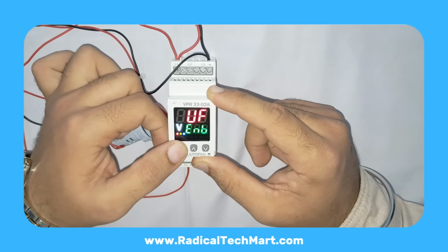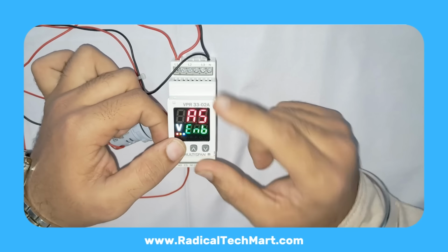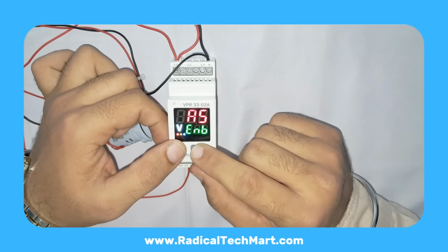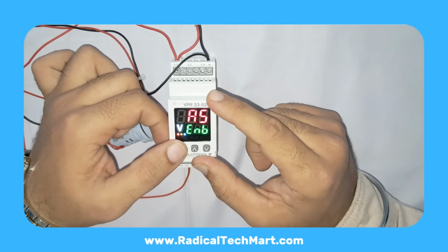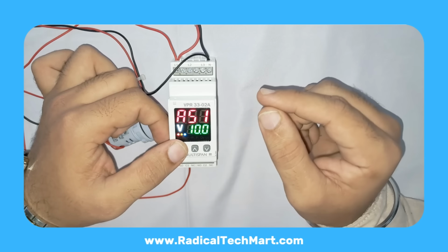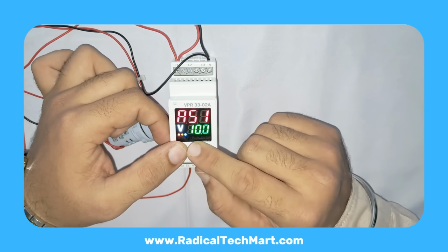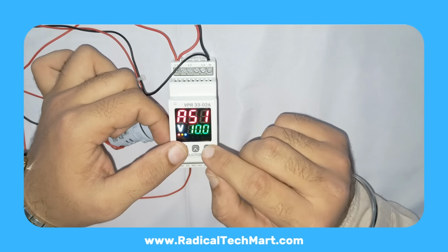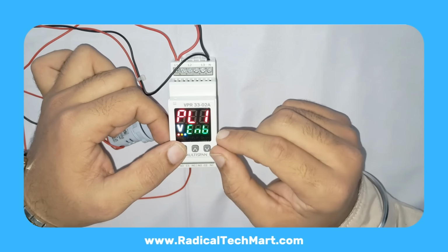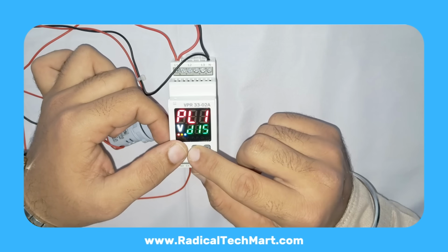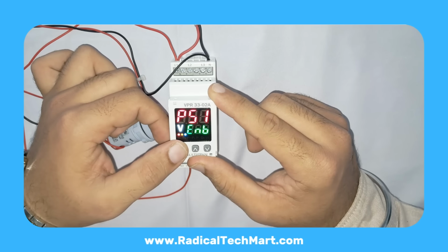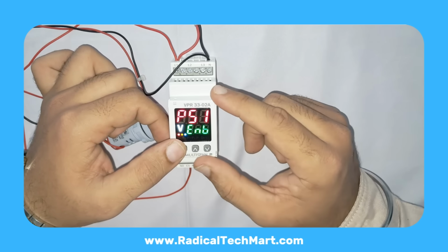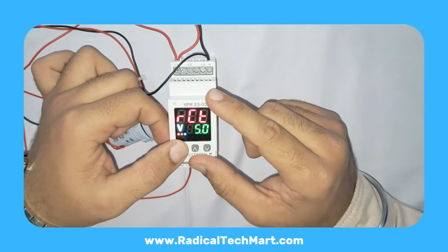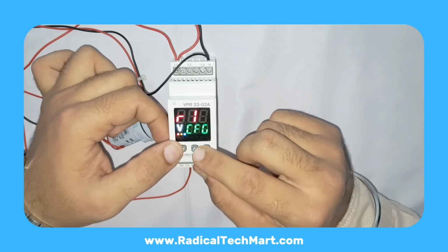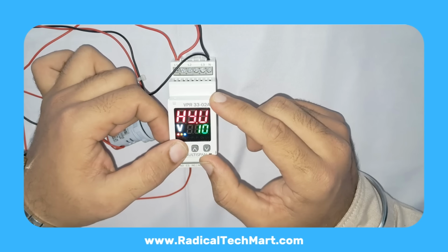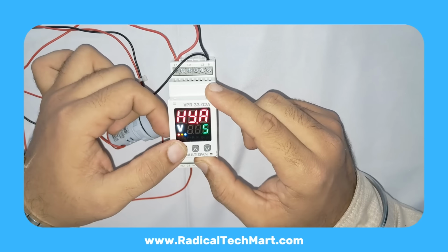Asymmetry, ASY. Phase loss and phase sequence. For asymmetry, you can enable or disable it. This monitors the voltage difference between phases. The default may be a 10-volt difference, which you can adjust. For phase loss, you can choose whether to detect and trip on loss of any phase. For phase sequence, you can enable/disable wrong phase sequence protection. When reset mode is in auto, you will also get hysteresis settings for asymmetry and for frequency.